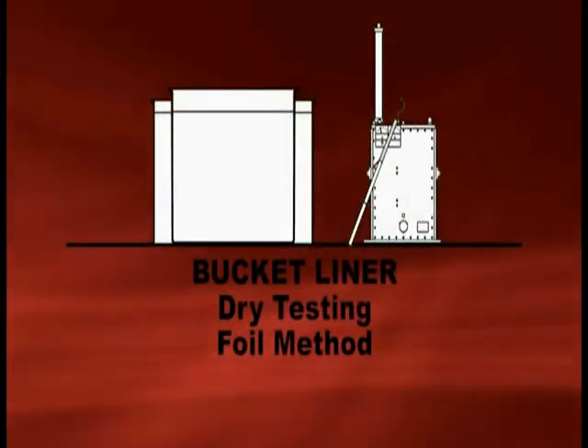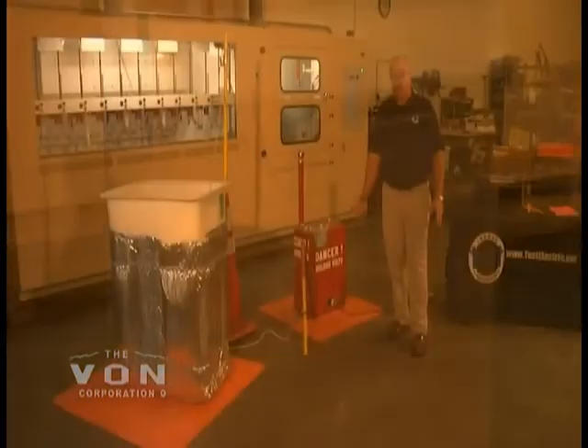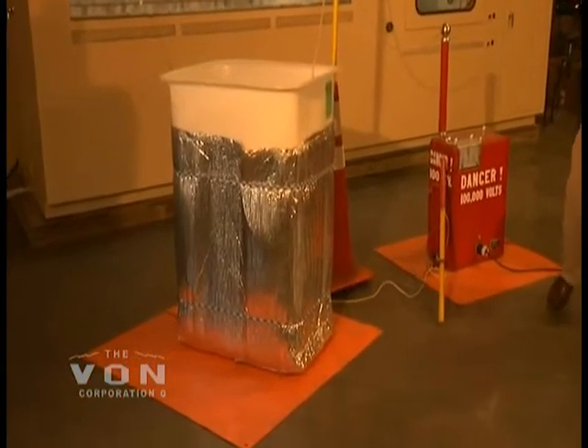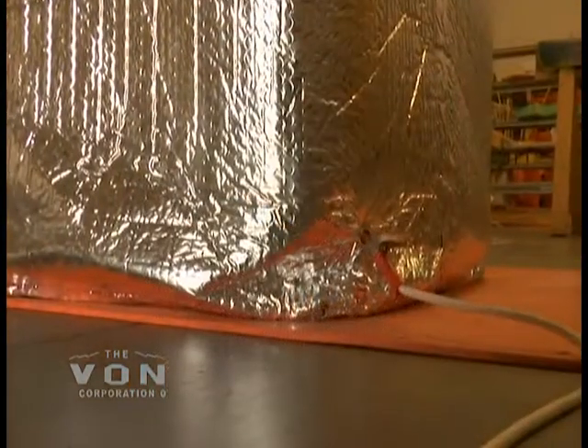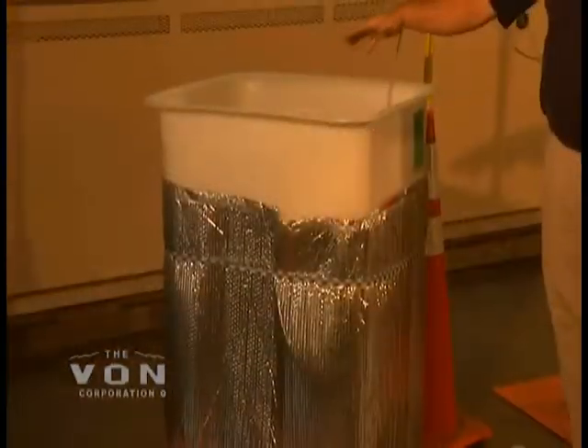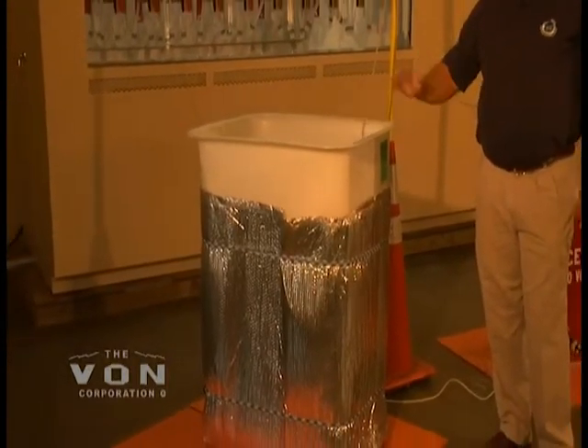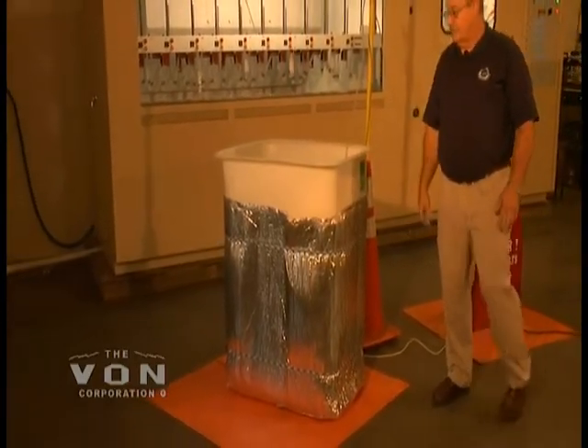There are two ways to test using the dry method: you can use the sock system or you can use the foil method. Both methods are effective. It's basically a conductor on the inside of the liner and a conductor on the outside of the liner. You ground the outside conductor and energize the foil conductor on the inside. The conductors cover the bottom and all four sides inside and out, with an arc gap to keep it from arcing. We are now ready to test this liner.